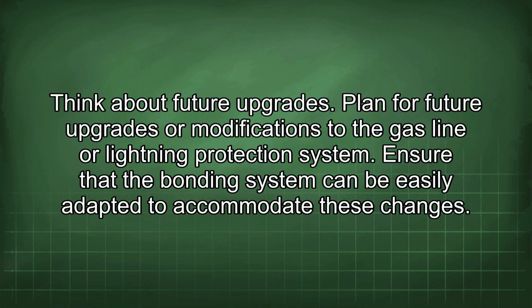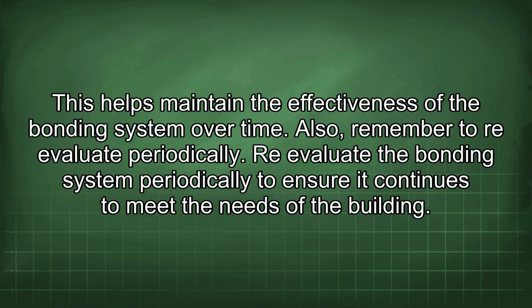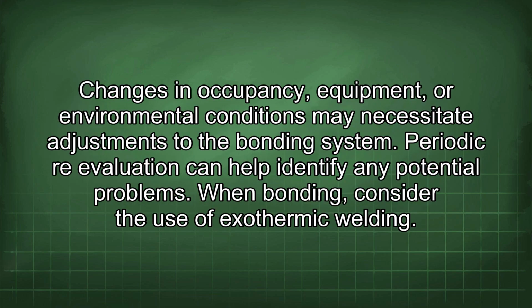Think about future upgrades. Plan for future upgrades or modifications to the gas line or lightning protection system. Ensure that the bonding system can be easily adapted to accommodate these changes. This helps maintain the effectiveness of the bonding system over time. Also, remember to reevaluate periodically. Reevaluate the bonding system periodically to ensure it continues to meet the needs of the building. Changes in occupancy, equipment, or environmental conditions may necessitate adjustments to the bonding system. Periodic reevaluation can help identify any potential problems.